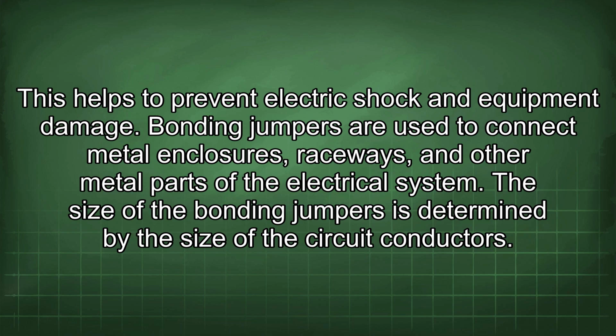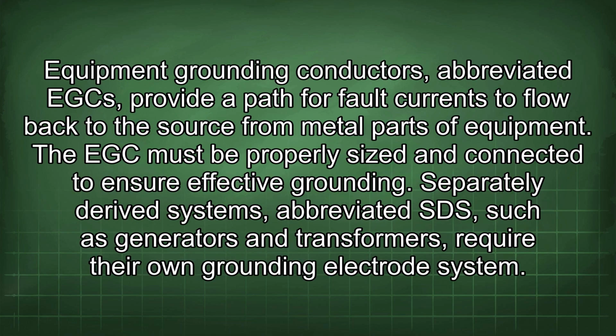Bonding jumpers are used to connect metal enclosures, raceways, and other metal parts of the electrical system. The size of the bonding jumpers is determined by the size of the circuit conductors. Equipment grounding conductors, abbreviated EGC, provide a path for fault currents to flow back to the source from metal parts of equipment. The EGC must be properly sized and connected to ensure effective grounding.